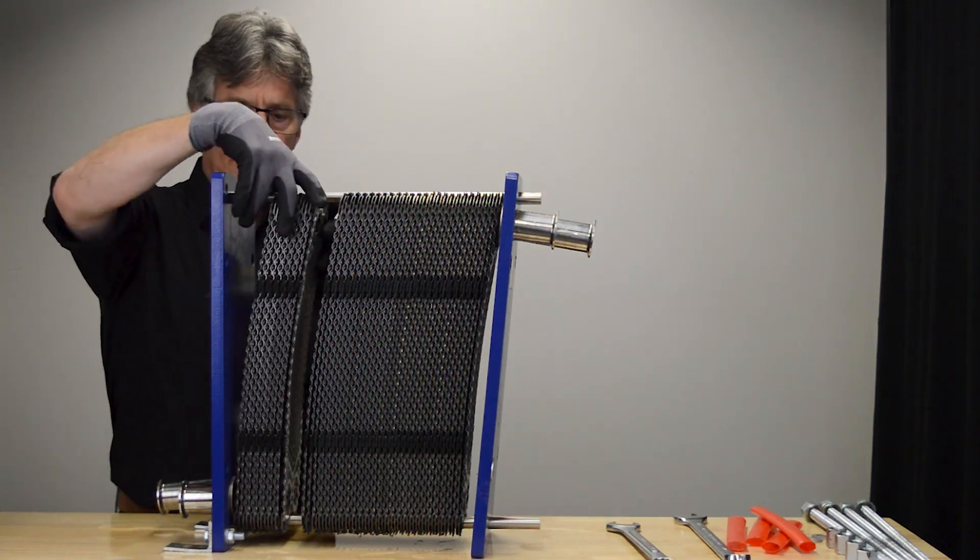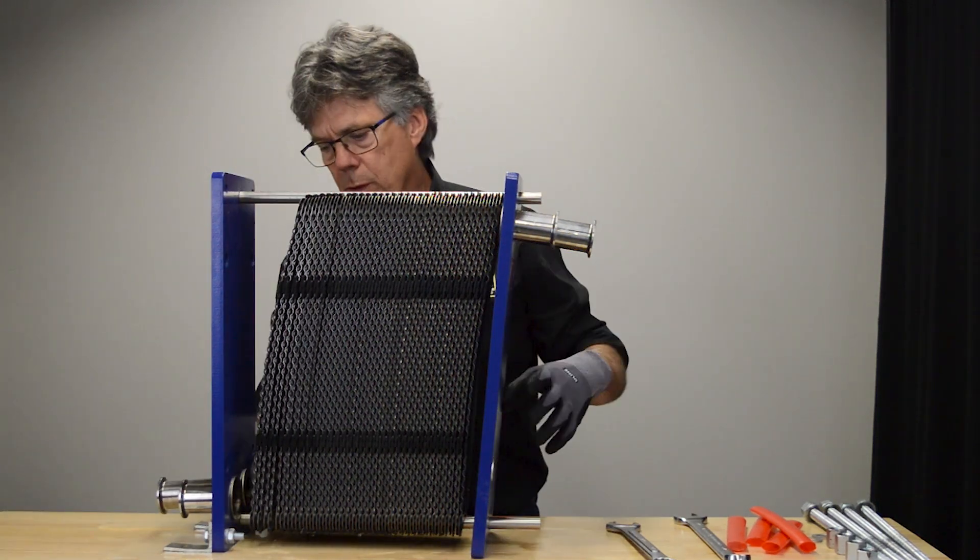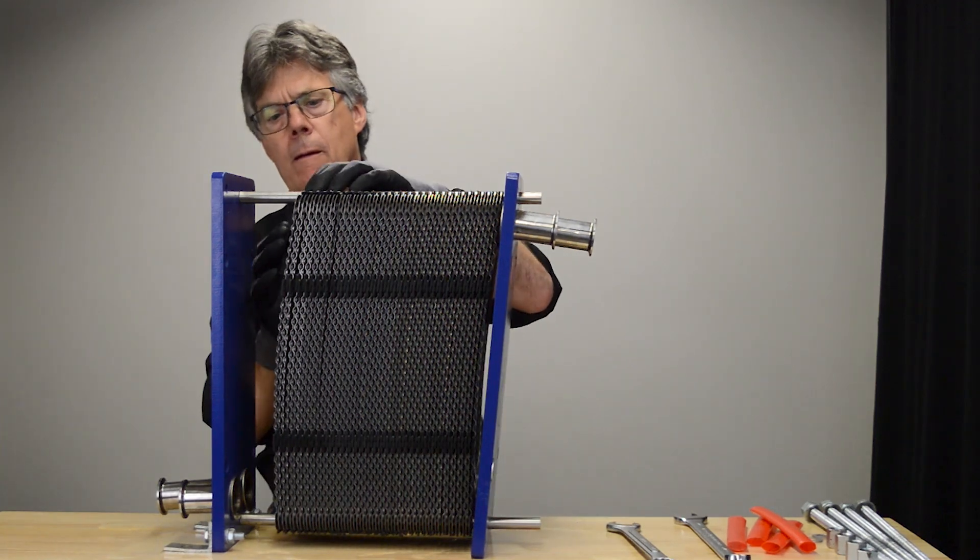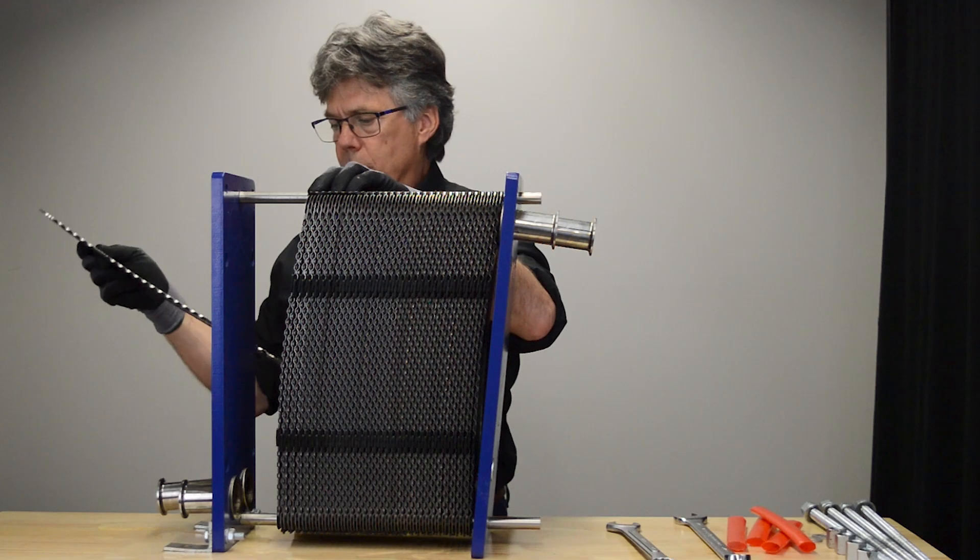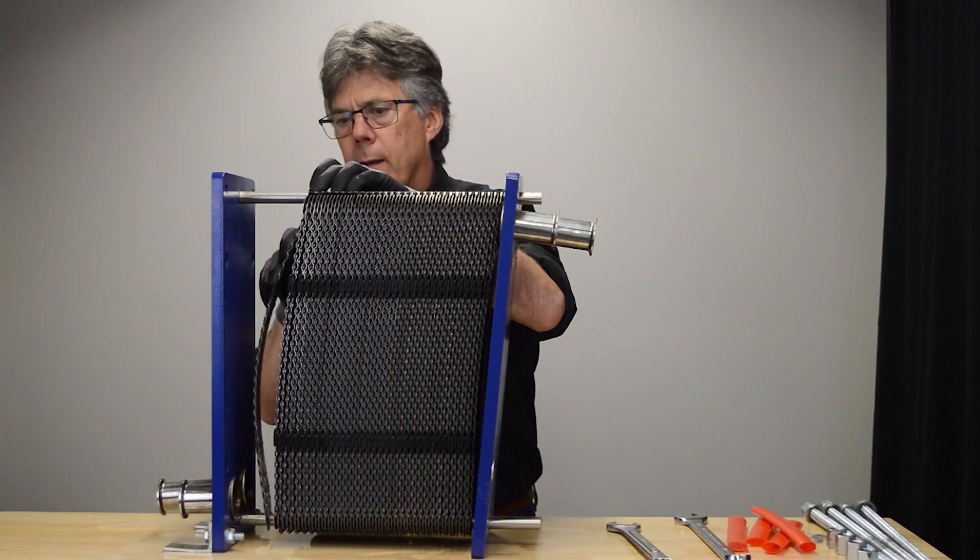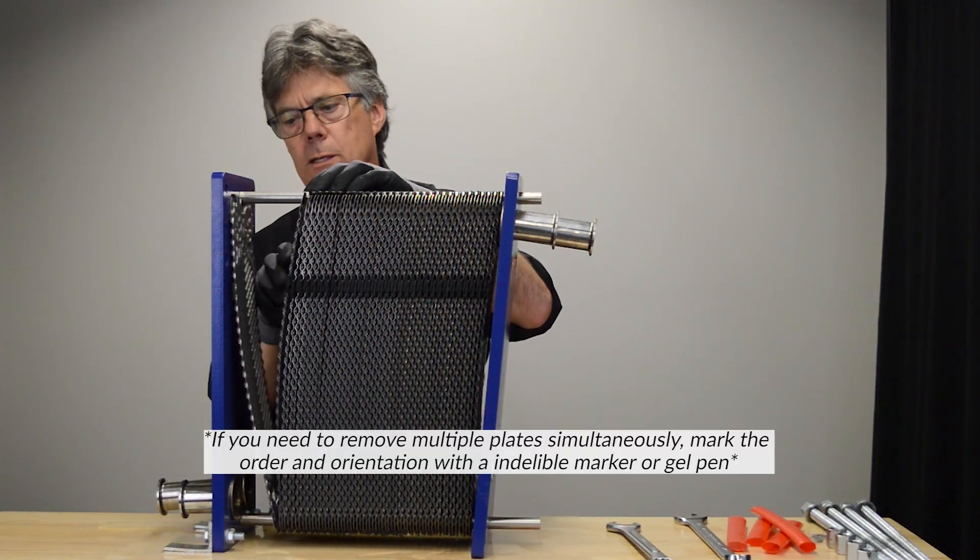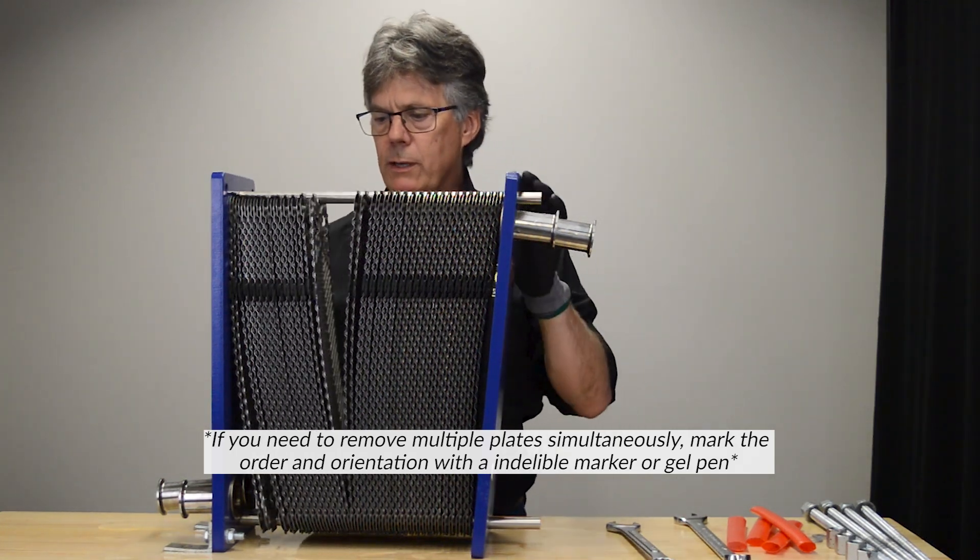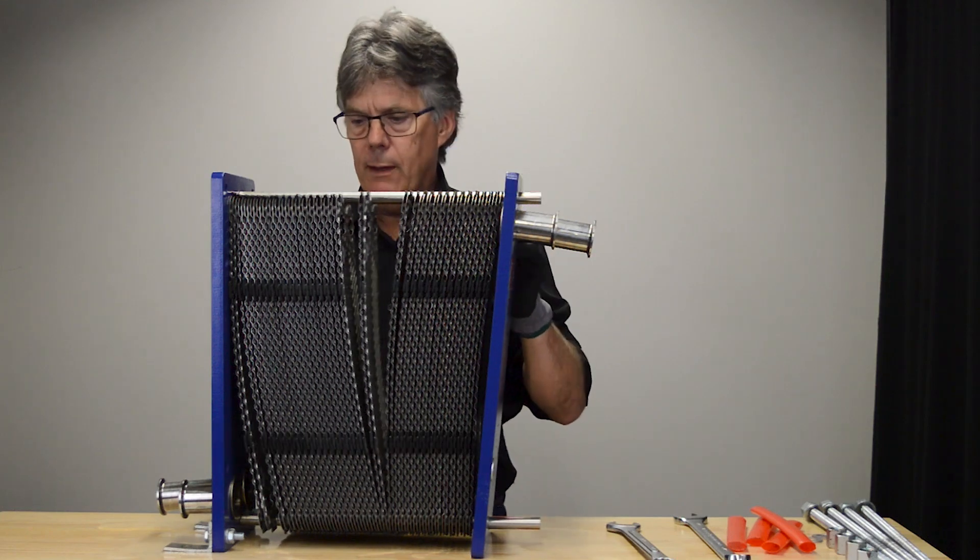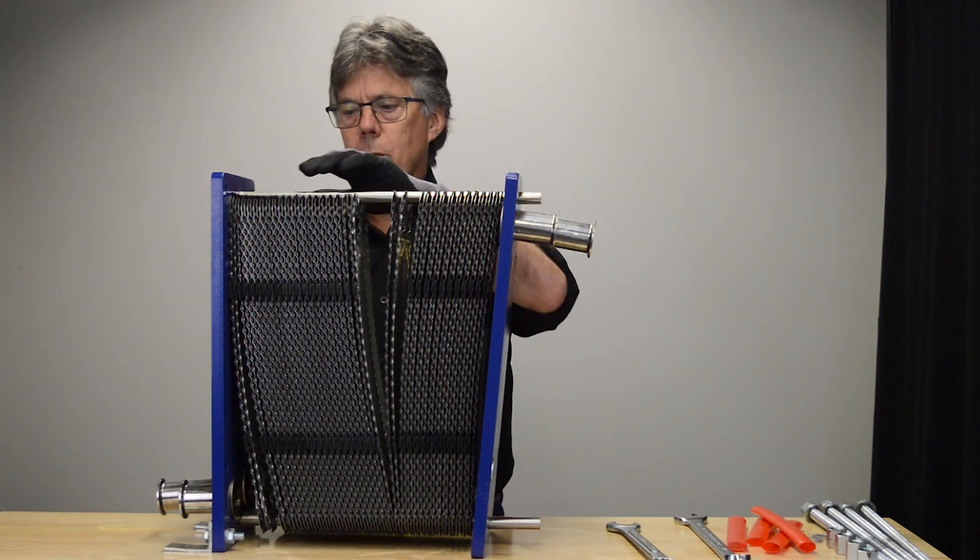So if we were changing the gasket or cleaning the heat exchanger, we'd start with this end, we'd take one plate out, we'd wash it, put it back in again, and then we'd do the next one and keep going through. If we take them all out and throw them all in the bathtub or the wash sink at the same time, then we're going to get them mixed up, and when we put them back together, it's not going to work.